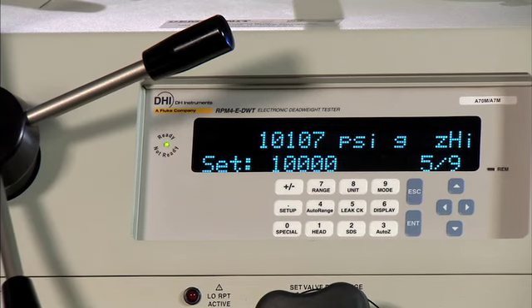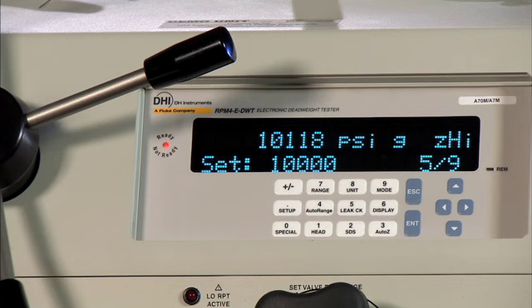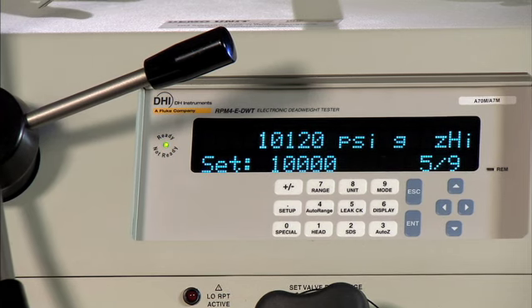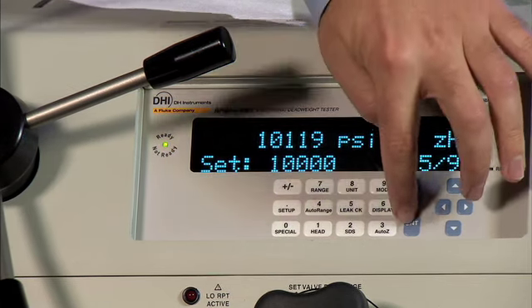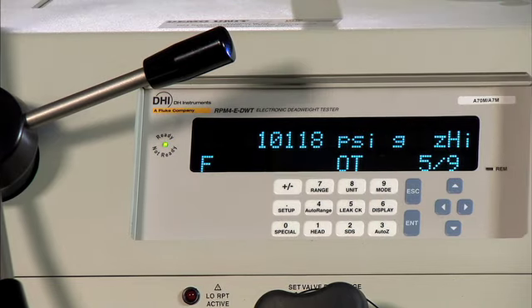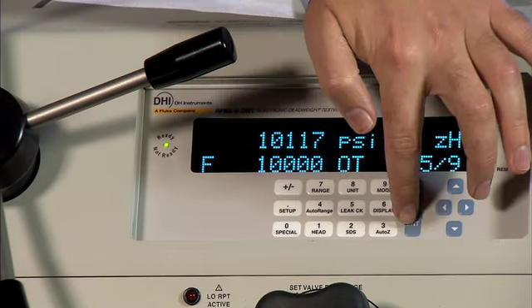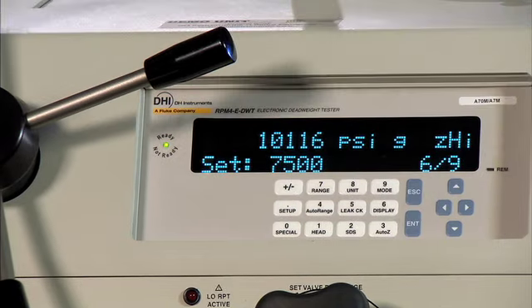So let's bring it back up to 10,000 psi and see if we're ready. We are ready. I'm going to go ahead and push enter, and it's out of tolerance. So now I'm going to push enter one more time to acknowledge that. And now we're going to go back to 7,500 psi.